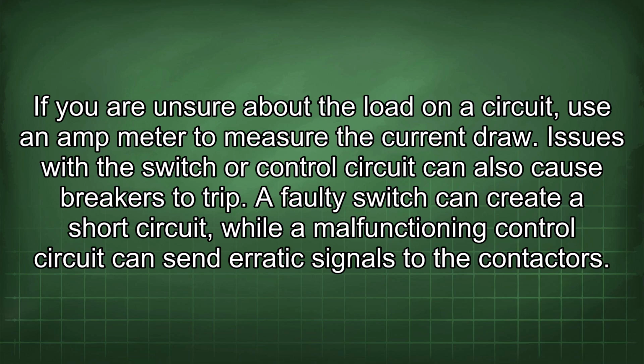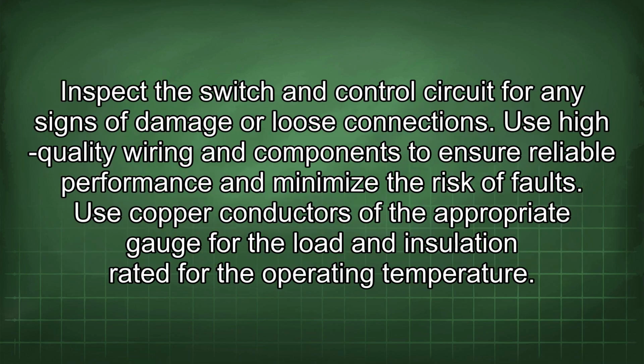Issues with the switch or control circuit can also cause breakers to trip. A faulty switch can create a short circuit, while a malfunctioning control circuit can send erratic signals to the contactors. Inspect the switch and control circuit for any signs of damage or loose connections. Use high-quality wiring and components to ensure reliable performance and minimize the risk of faults.